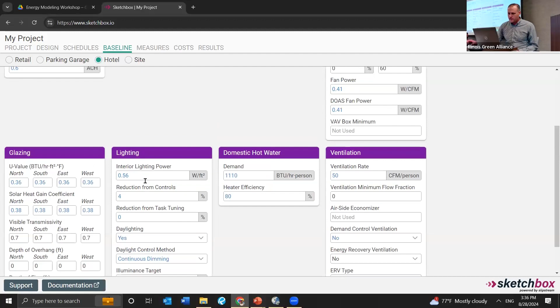There are some things here that are not code regulated. A big one is miscellaneous equipment power - we've pulled this value based on our judgment from other sources. So not everything comes from code, but we've tried to provide good starting points for all this stuff. Infiltration is a big one - that's starting to become code regulated, especially for individual assemblies, but in general this is a big unknown with energy models. How leaky is this building? 0.6 air changes per hour is probably a decent assumption for a new building. If you're working with an old building, I've seen this as high as 3 to 5 air changes an hour for a very leaky building, and I've also seen new buildings with much lower values if contractors and designers spend the time to achieve that.